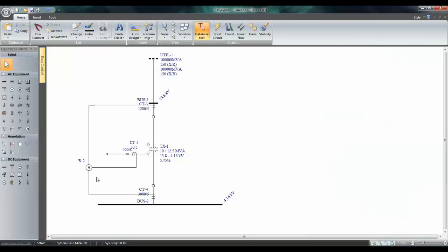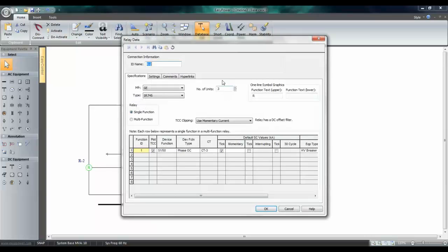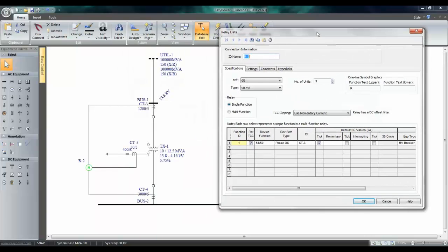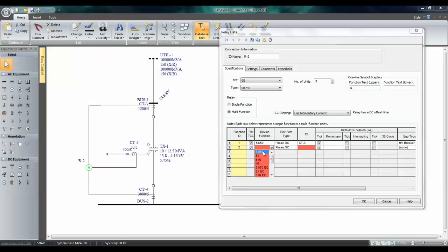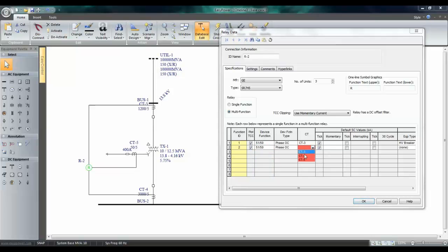Next, I'm going to enter data for the overcurrent protection on the secondary side. So, I have to choose multifunction, and then function ID 2. Again, this is going to be 5150, and this is going to be fed by CT number four.